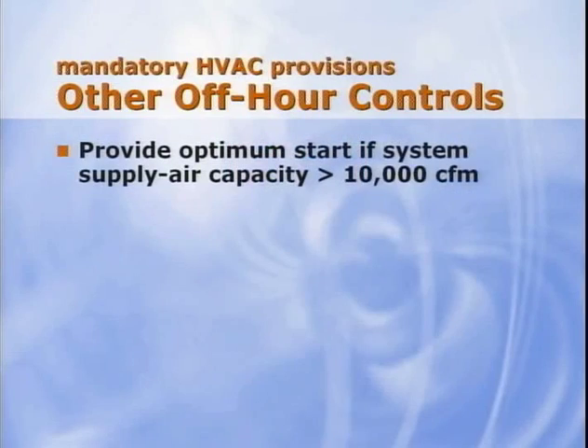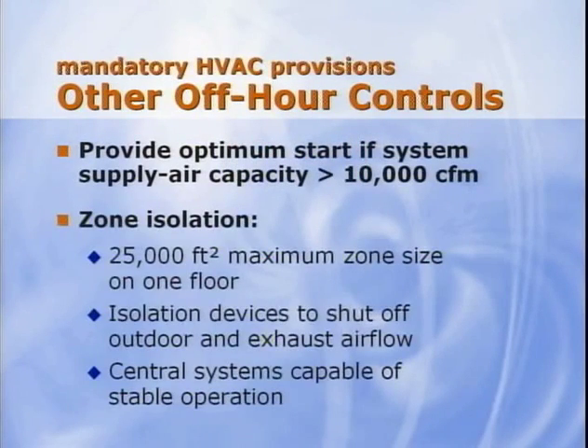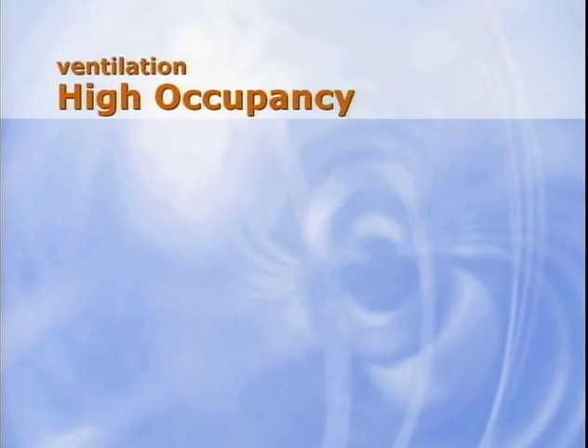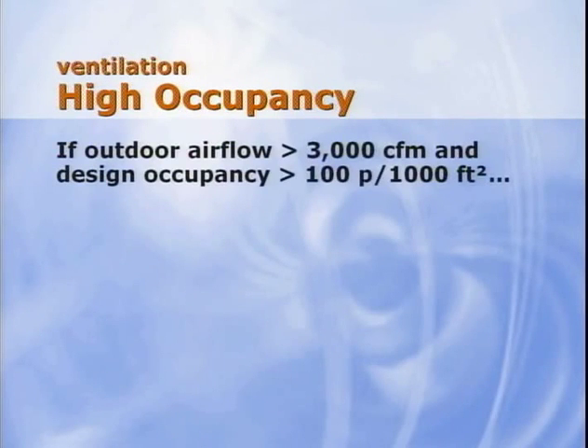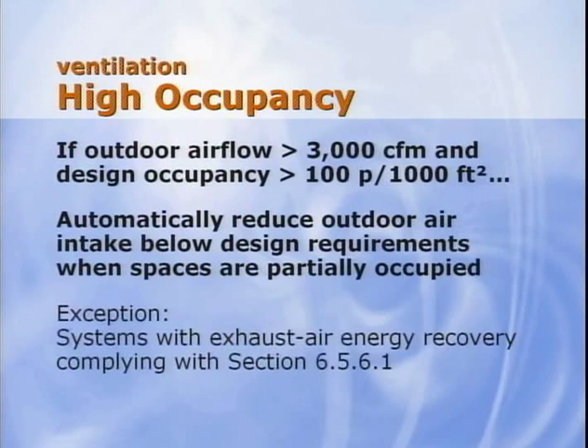Optimum start is required once the system is greater than 10,000 CFM. Phil will cover this later. In large systems, during off hours, the system must be capable of reducing airflow by isolating areas of the building. This ensures that the entire air conditioning system doesn't have to function to satisfy a small area of the building. In spaces that have more than 3,000 CFM and high occupancy, the system must be able to automatically reduce outdoor air intake when the spaces are partially occupied.